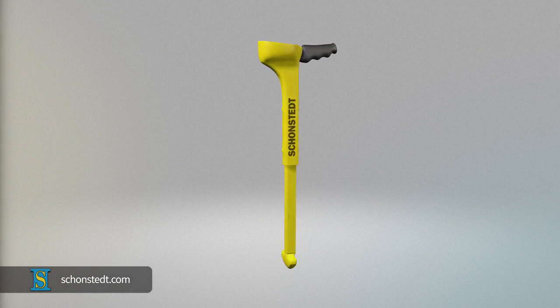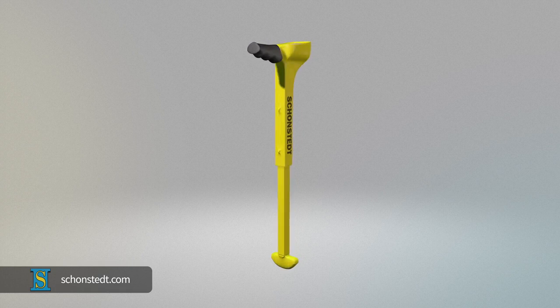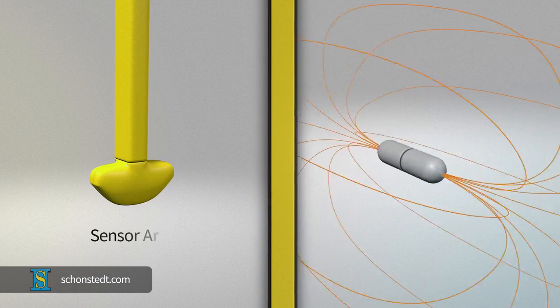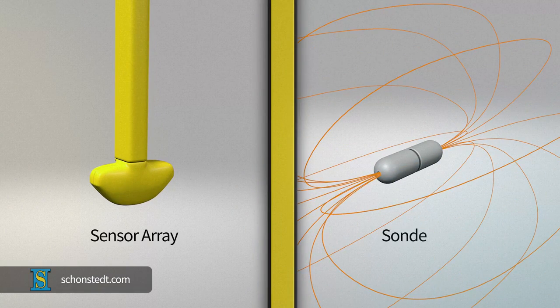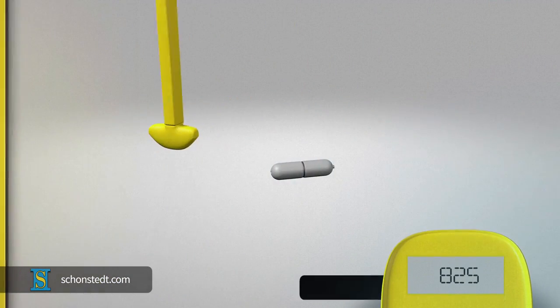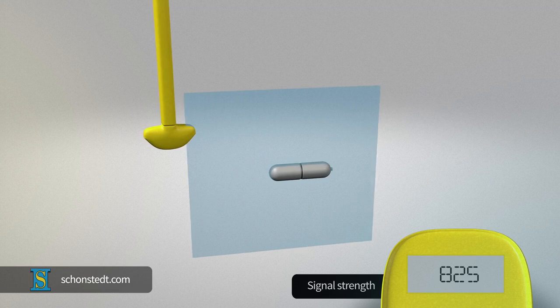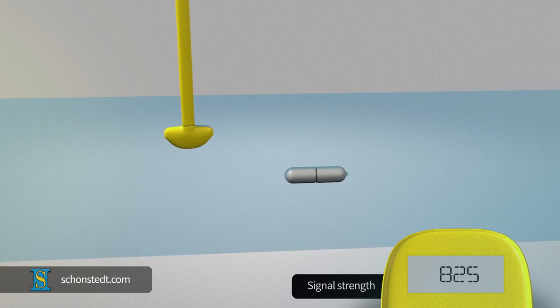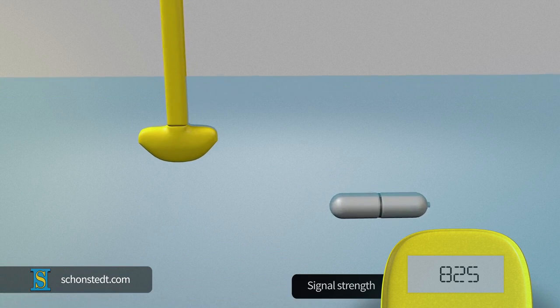In order to understand the techniques for approaching and pinpointing, it is important to understand the relationship between the orientation of the receiver sensor array and the sonde. The signal detected by the sensor array is strongest or peak when the axis of the sonde and the axis of the sensors in the receiver are on the same plane.